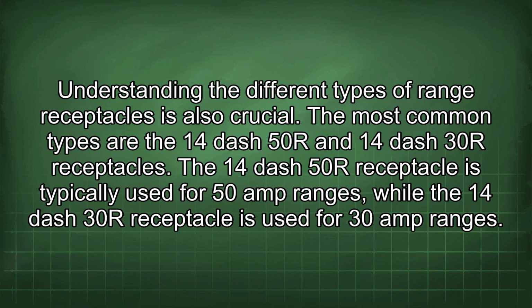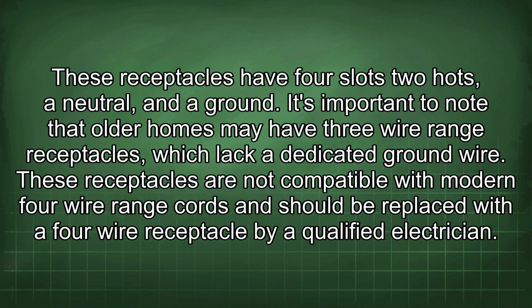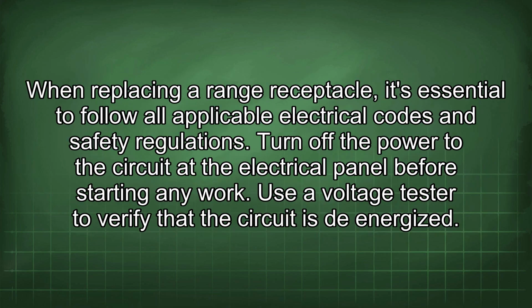The most common types are the 14-50R and 14-30R receptacles. The 14-50R receptacle is typically used for 50 amp ranges, while the 14-30R receptacle is used for 30 amp ranges. These receptacles have 4 slots: 2 hot, a neutral, and a ground. It's important to note that older homes may have 3-wire range receptacles which lack a dedicated ground wire. These receptacles are not compatible with modern 4-wire range cords and should be replaced with a 4-wire receptacle by a qualified electrician.